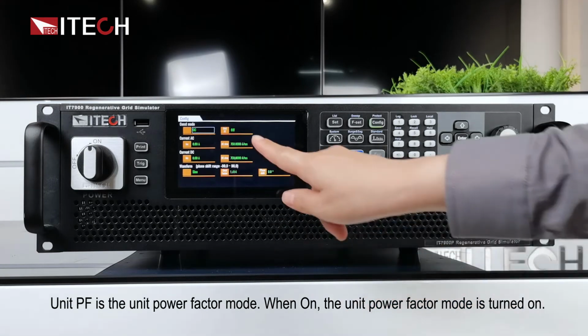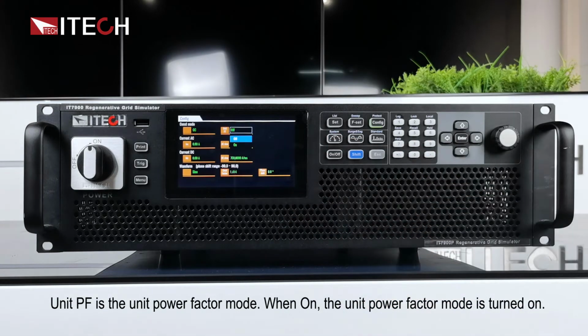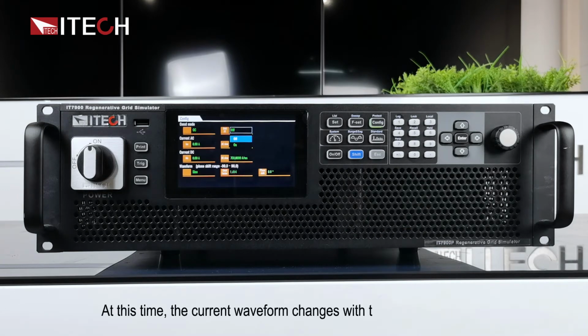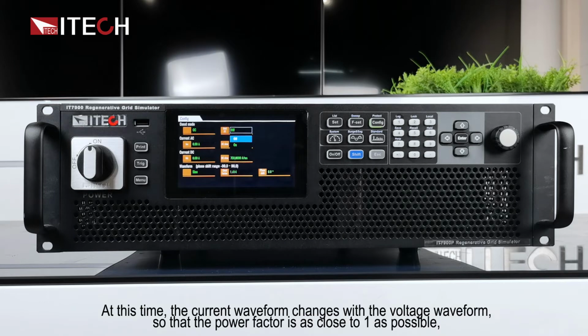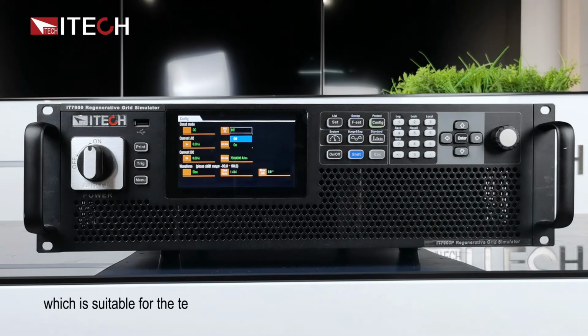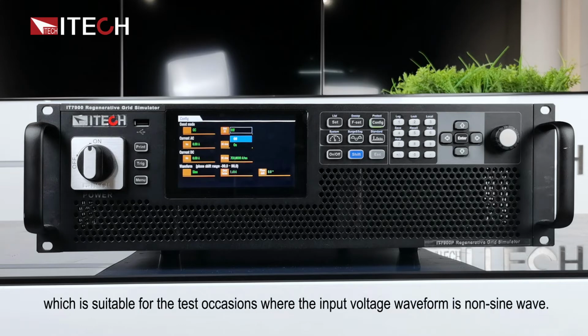Unit PF is the unit power factor mode. When on, the unit power factor mode is turned on. At this time, the current waveform changes with the voltage waveform so that the power factor is as close to 1 as possible, which is suitable for the test occasions where the input voltage waveform is non-sine wave.